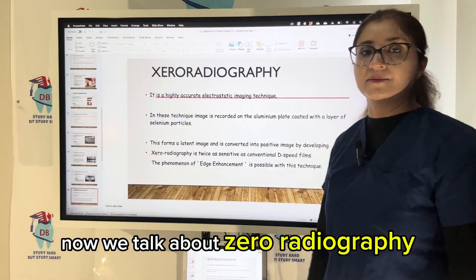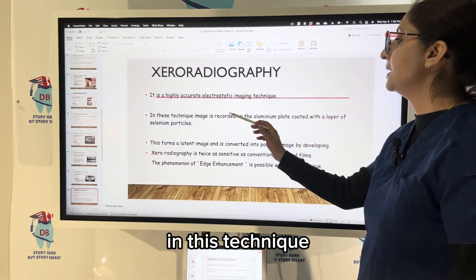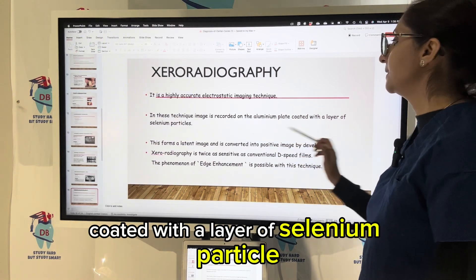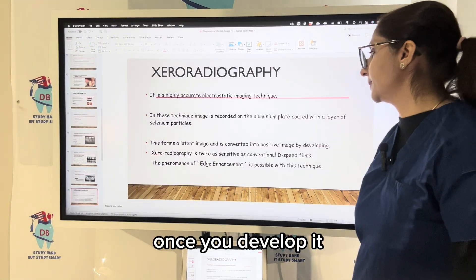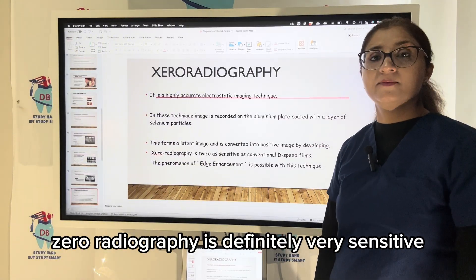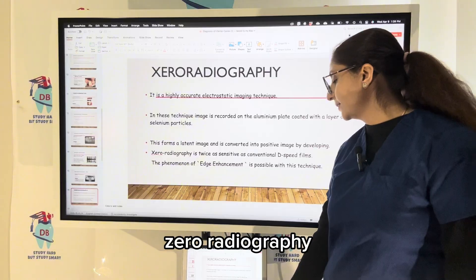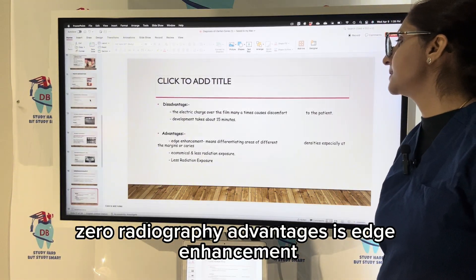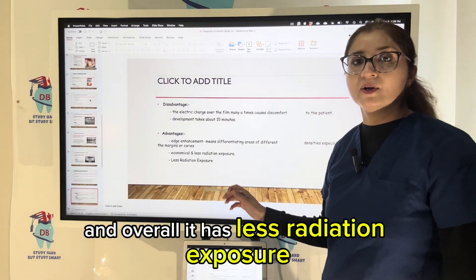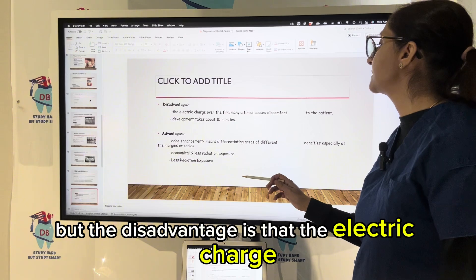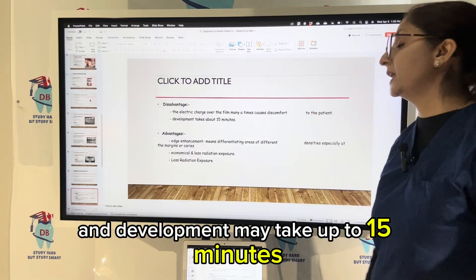Xeroradiography is an advanced, highly accurate electrostatic imaging technique. In this technique, the image is recorded on an aluminium plate coated with a layer of selenium particles, forming a latent image that is converted into a positive image once developed. Xeroradiography is twice as sensitive as conventional D-speed film. The phenomenon of edge enhancement is possible, helping to differentiate areas of different margins of caries. It is economical with less radiation exposure. The disadvantage is that the electric charge over the film can cause discomfort to the patient, and development may take up to 15 minutes.